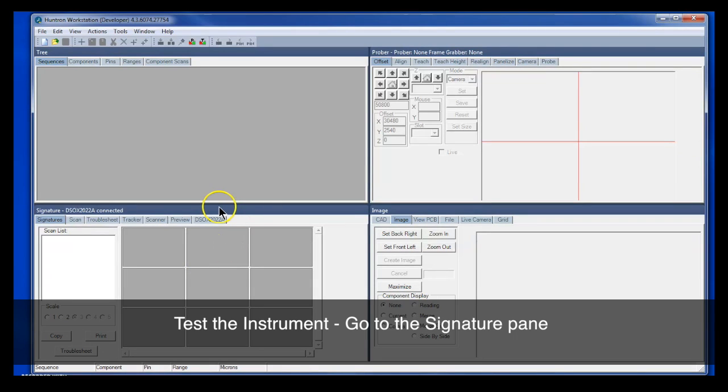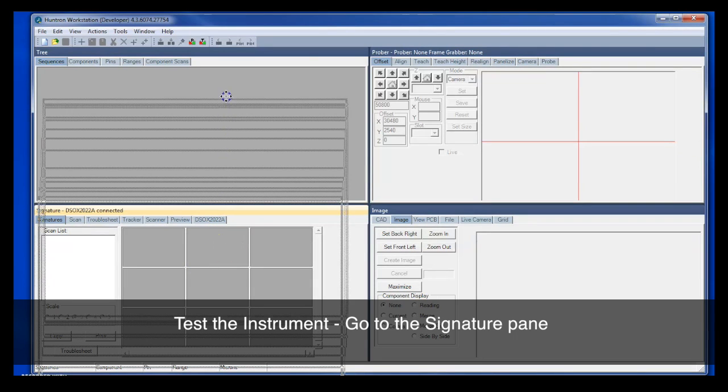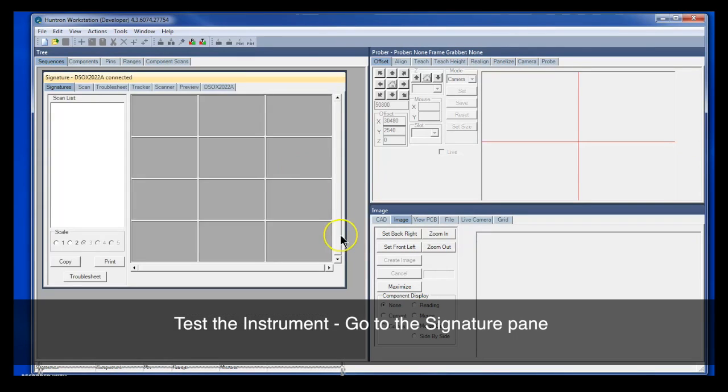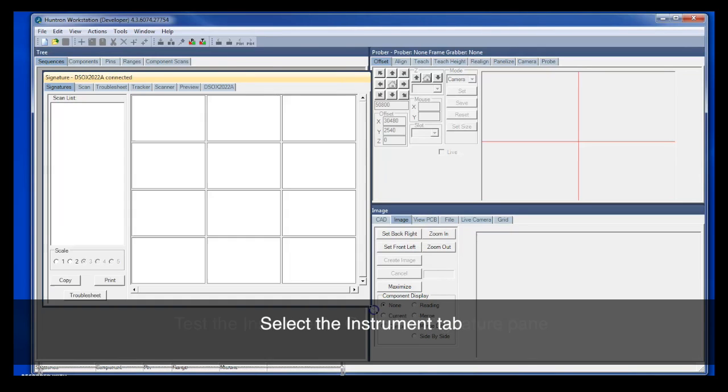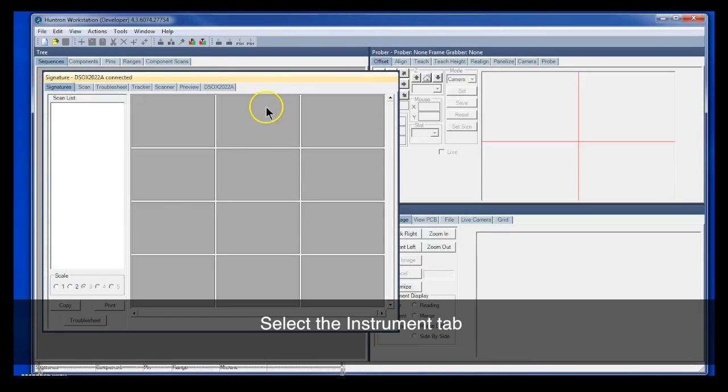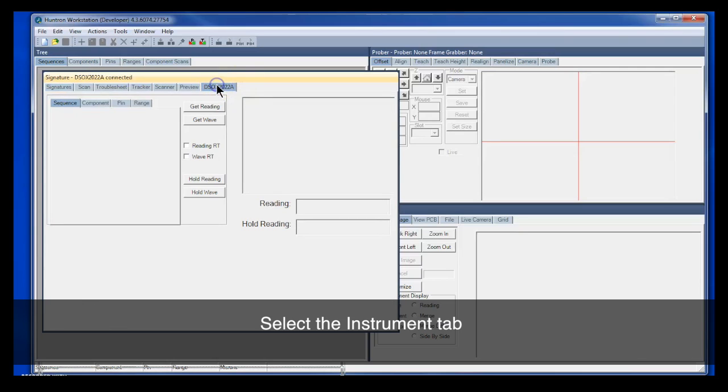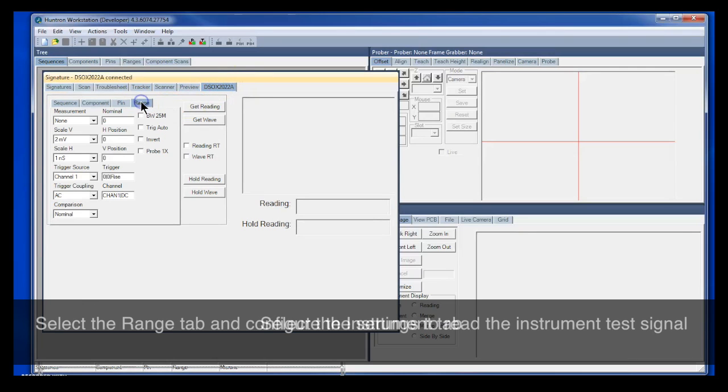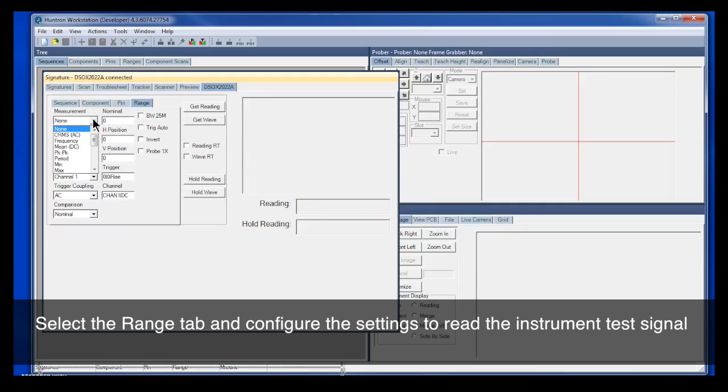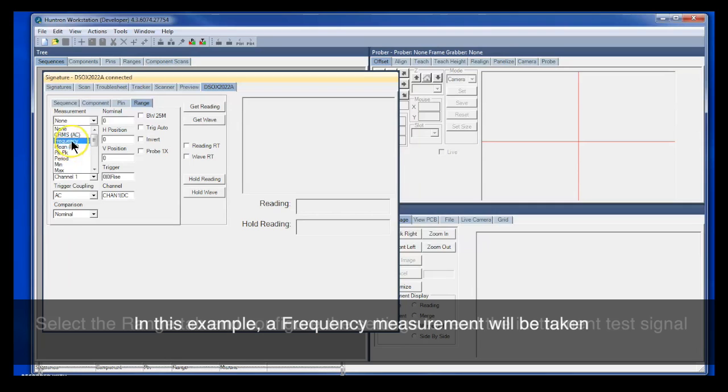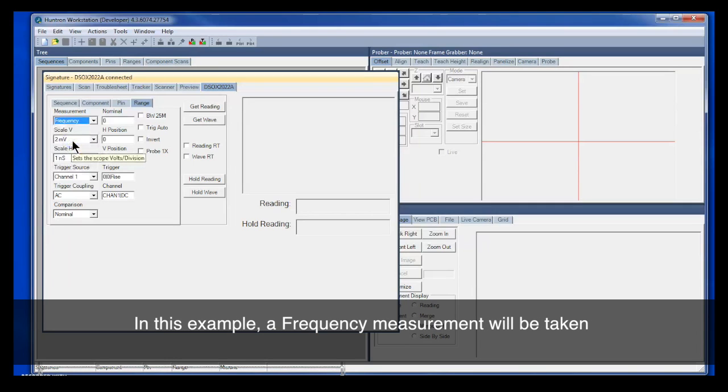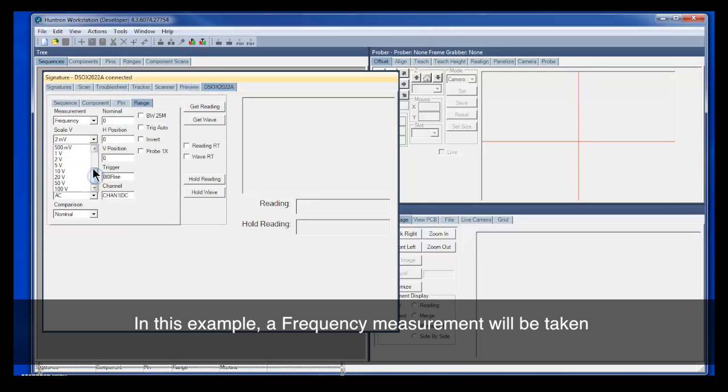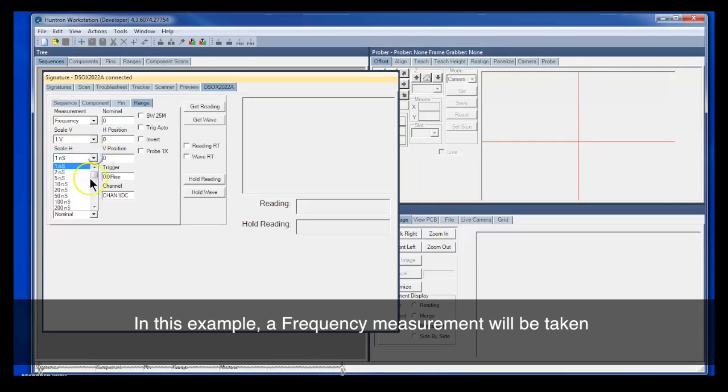And now in Workstation, you go to the Signature pane and select your new instrument tab that should show up here. This is for our Keysight oscilloscope. Select the Range tab, and we're just going to take a simple frequency measurement from the test output on the oscilloscope. So let's select Frequency, and then we'll set up the Horizontal and Vertical scales.